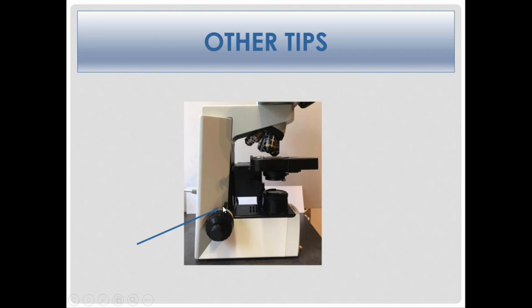Another thing that can disrupt the delicate settings of your microscope is vibration. So if you have a centrifuge in your lab, try not to have it on the same table as your microscope. If that is unavoidable, place the centrifuge on a rubber mat to absorb the vibrations as much as possible, and indeed the noise as well, making the lab a nicer place to work in. Your microscope will be less shaken around, and therefore last longer.